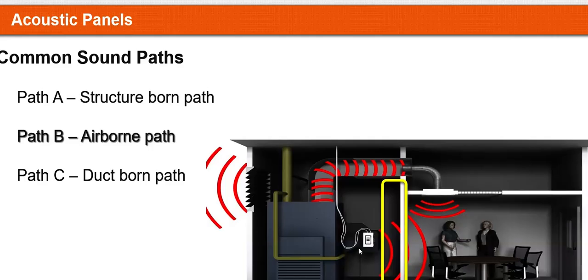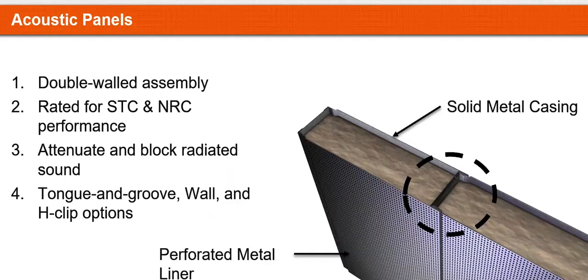So what happens to your radiated noise when the fan ramps up? Your radiated noise is going to increase, aka exposed applications. You have fan power boxes in a space, and all of a sudden you add inlet silencers and discharge silencers, and you still have noise complaints. Well, that's because you are increasing your radiated noise by 2 to 3 decibels, single number rating. And for that, you add mass. You have to add an enclosure or a ceiling or a cloud ceiling with enough transmission loss to get to a certain sound level in the space. What we typically use to address that radiated sound is wall mount panels, double wall panels, which will have a rating for STC and NRC, and we're going to talk about what that means.